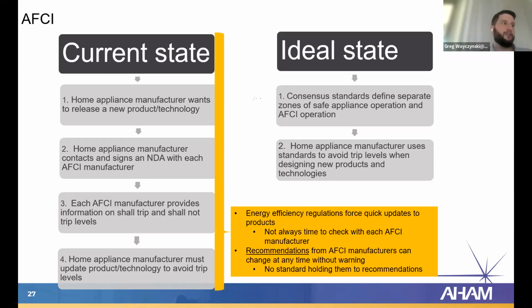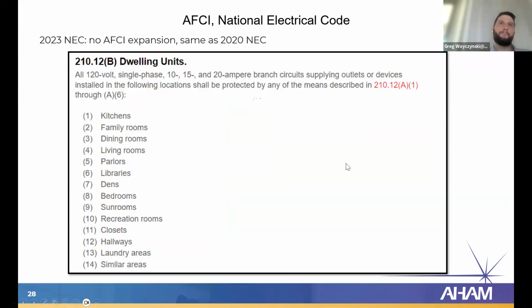Of course, we're getting resistance from AFCI manufacturers, but we're trying to get to the ideal state where there's a consensus standard that's open to everybody, that defines exactly when an AFCI must trip, and then home appliance manufacturers can use those standards to avoid those trip levels.